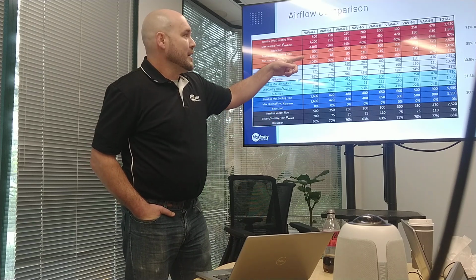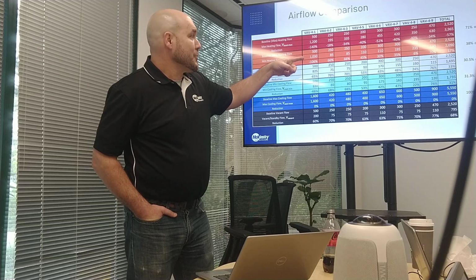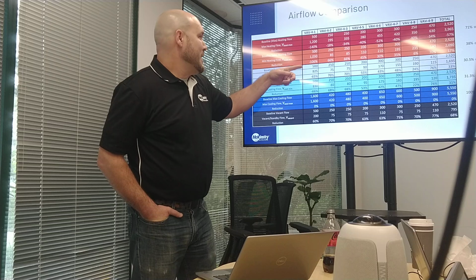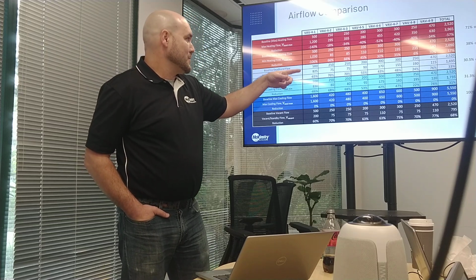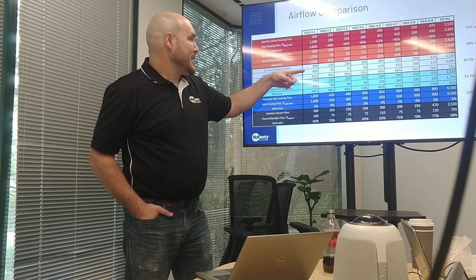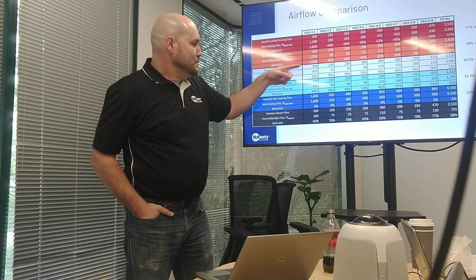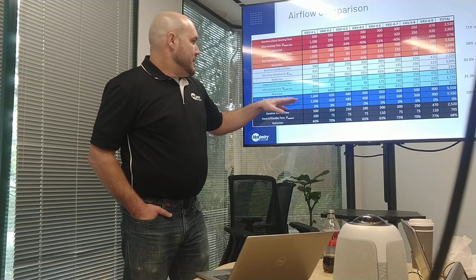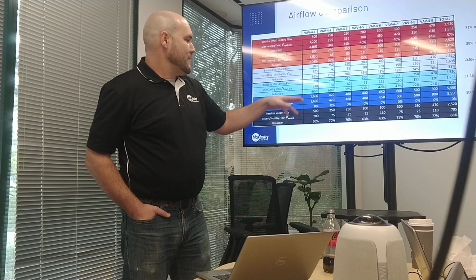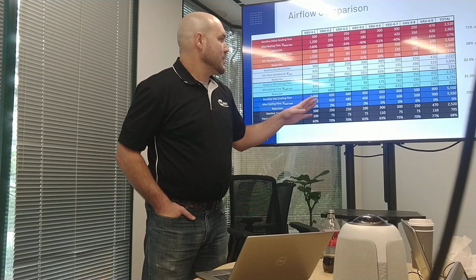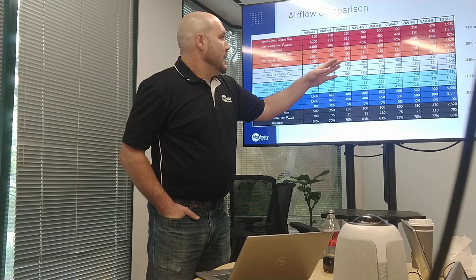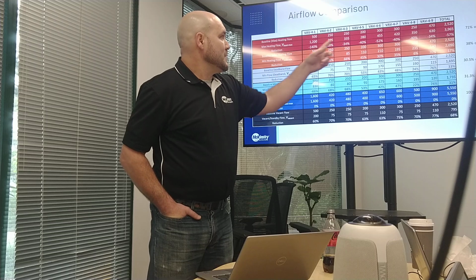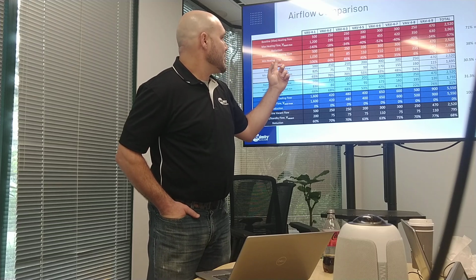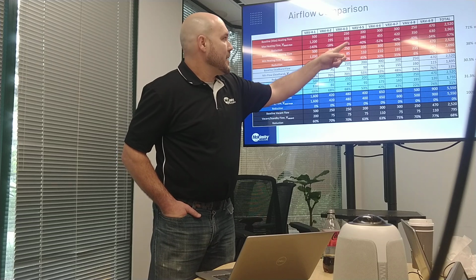Same thing for the baseline heating flow. It was 1,022, so I rounded this up to 1,030. Yeah, well, they weren't ventilating adequately, even in their minimum situation. And this VAV41 shows that, yeah, they weren't ventilating adequately. Pick any of these others though and see, well, it looks like they weren't ventilating adequately for most of these in the heating scenario. But when you go to the baseline minimum, and again, this 280, this is kind of the 70% of the max cooling airflow for that box.